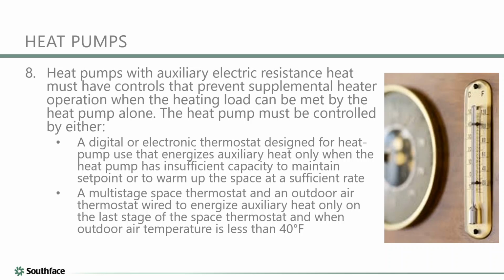And also, just to add to that, from an equipment standpoint, heat pumps are typically designed to work down to about 20 degrees Fahrenheit before they start struggling capacity-wise. So you'll get probably most of your capacity all the way down to 20, 25 degrees outside. Anything below that, 10 degrees, then it starts struggling to keep up with the load. And Hugh, is it true that typically the more efficient the heat pump gets, the lower that magic temperature number becomes?